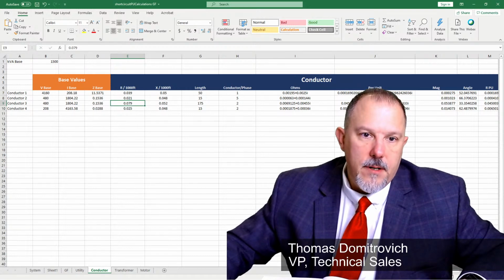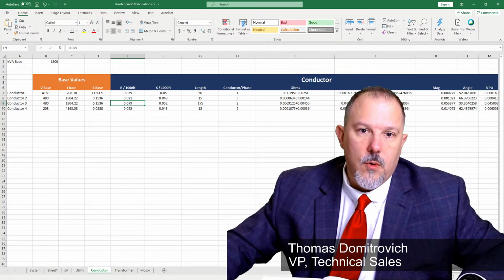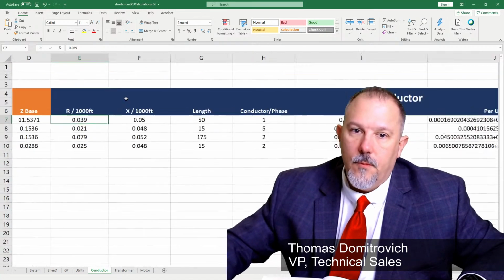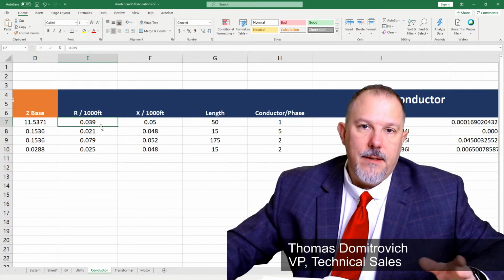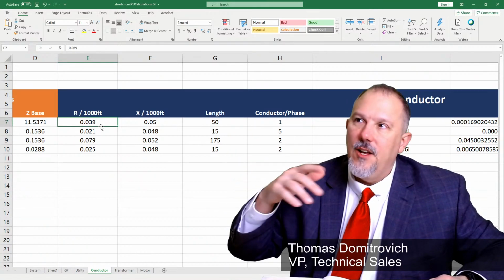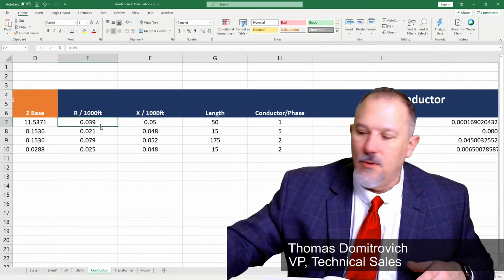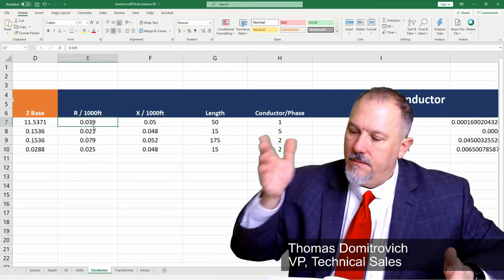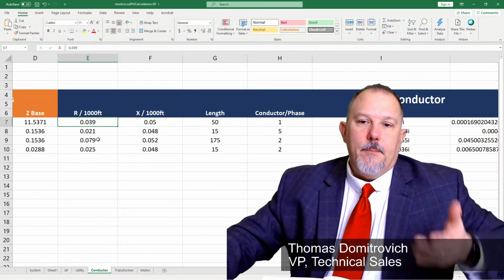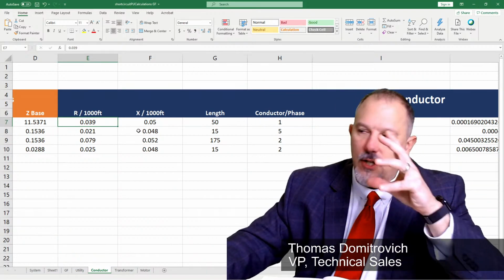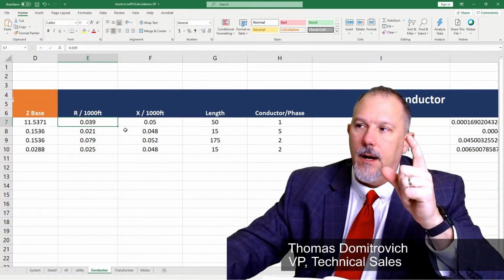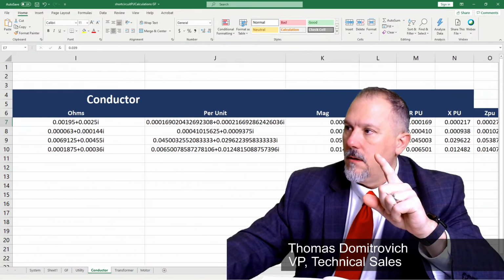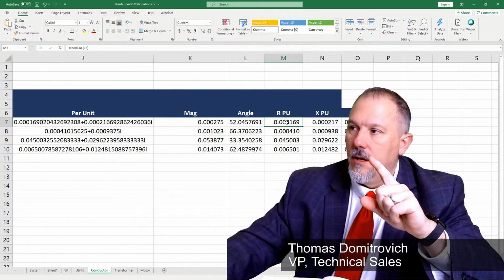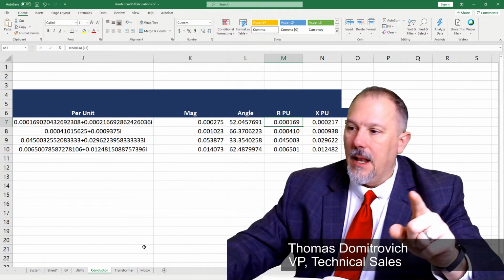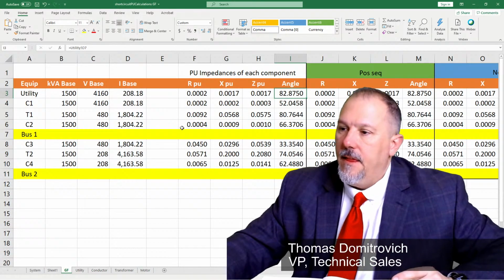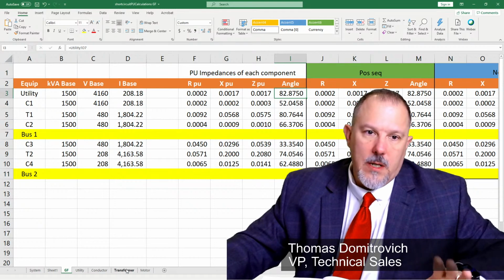In the conductor tab, I've got my conductors 1, 2, 3, and 4, and I calculate my resistance. What's nice about the spreadsheet is that the calculator introduces some error. So yeah, I'm 15 amps off. That's rounding errors. But I have all of the equations in here to show you how I got the per unit values for each of the conductors based upon the lengths. And I don't have to worry about the motor because we didn't model the motor.